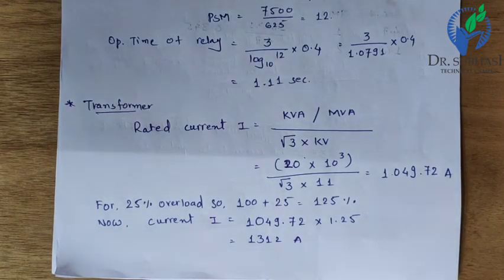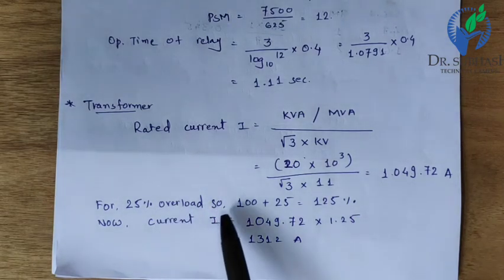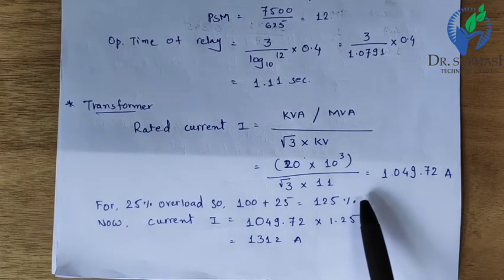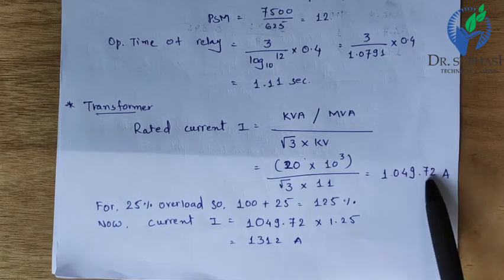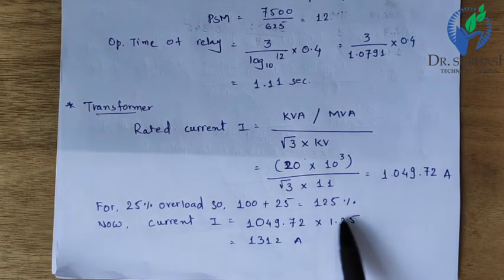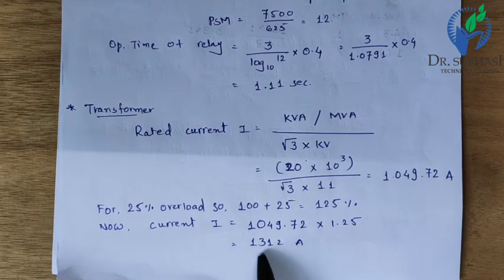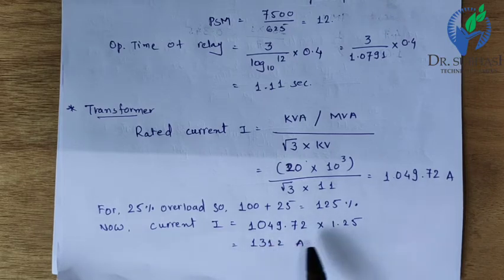With 25% overload, the transformer runs continuously at 125% of rated current. So the actual current is 1049.72 × 1.25 = 1312 A flowing from the transformer to the feeder.